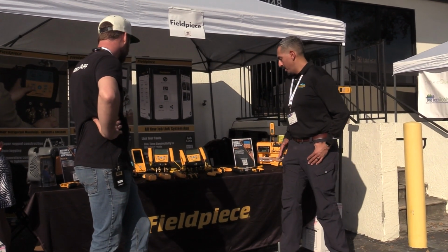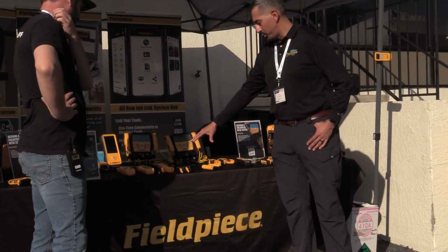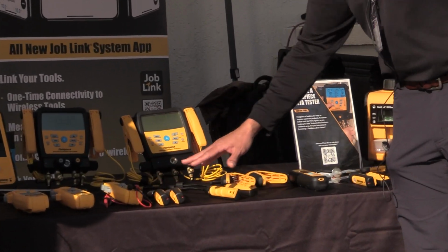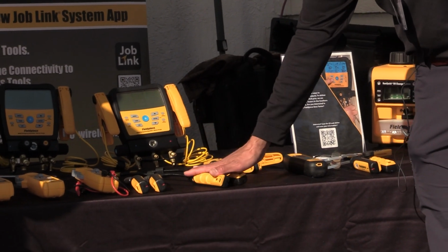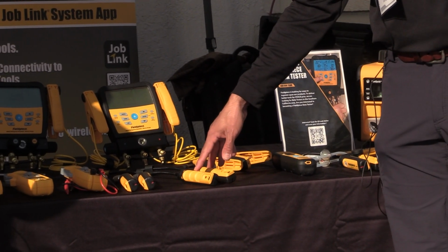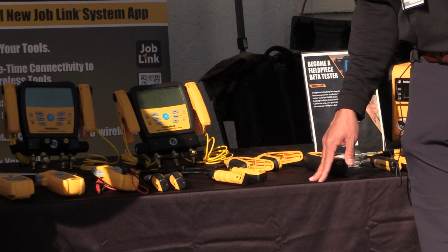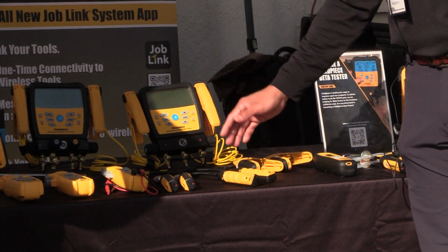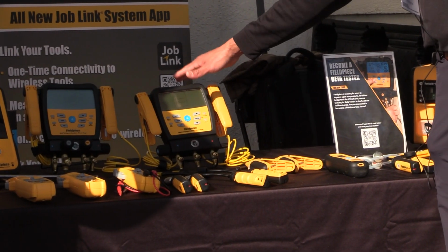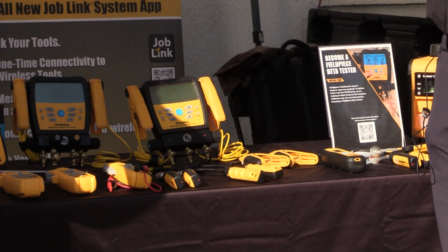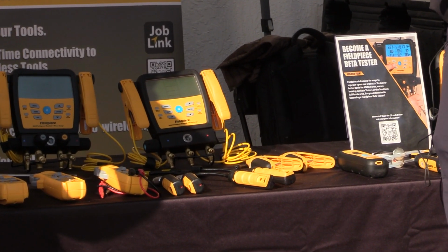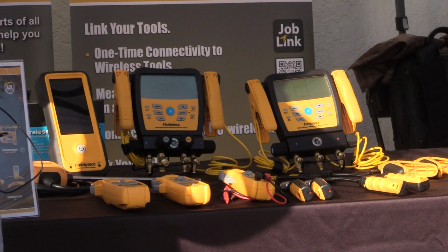You know our tried and true Job Link tools, which are our wireless pressure probes, pipe clamp, and digital psychrometers to measure your delta T, your temperatures at the return and supply. You'd use your pressure probes and pipe clamp just like you would a manifold, measuring suction line and liquid line pressures and temperatures, calculating superheat and subcooling.